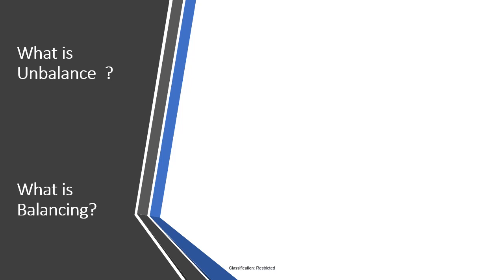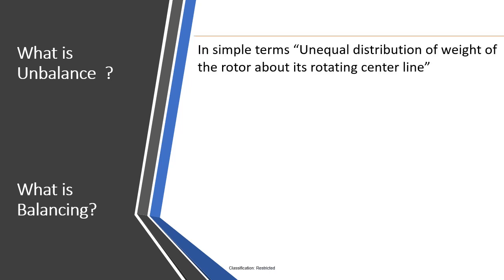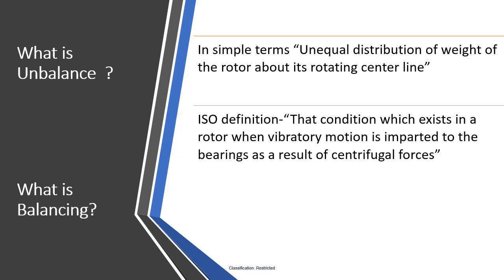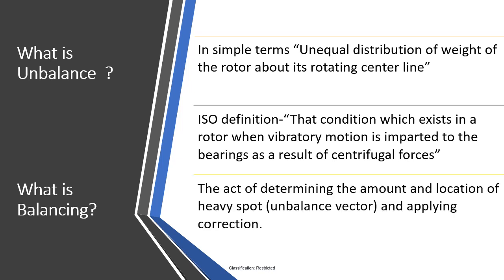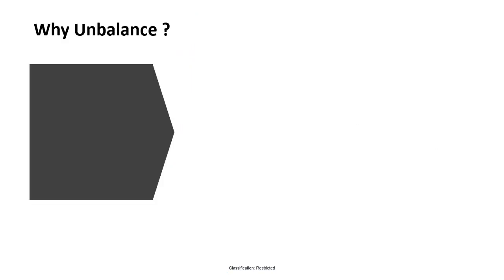What is unbalance? In simple terms, it is an unequal distribution of weight of the rotor about its rotating centerline. ISO defines unbalance as the condition which exists in a rotor when vibratory forces are imparted to the bearings as a result of centrifugal forces. Balancing is the act of determining the amount and location of the heavy spot and applying the correction — the heavy spot being the unbalance vector location in the rotor.